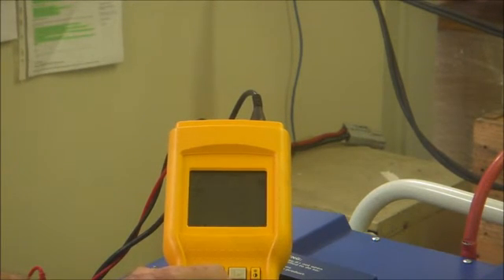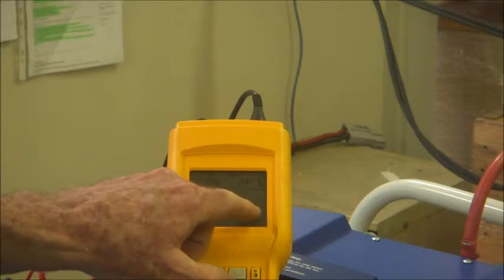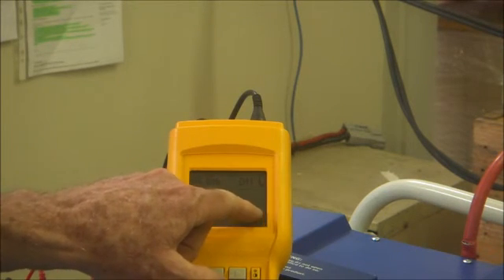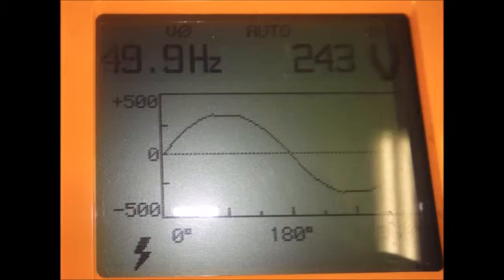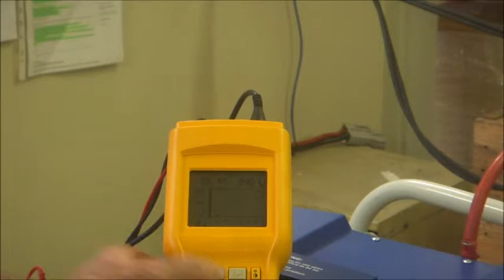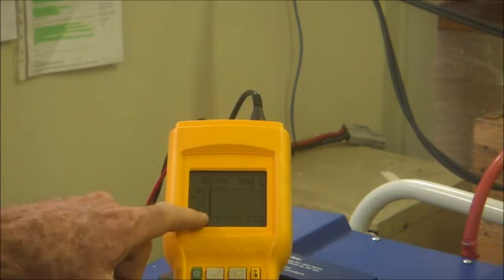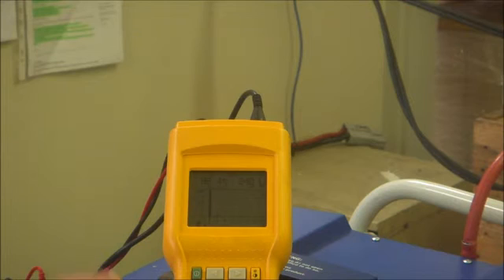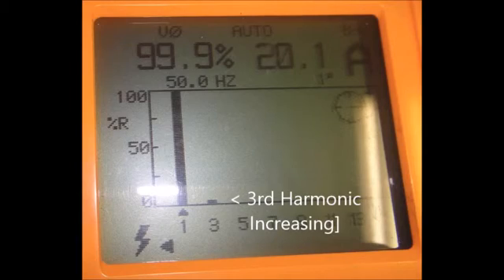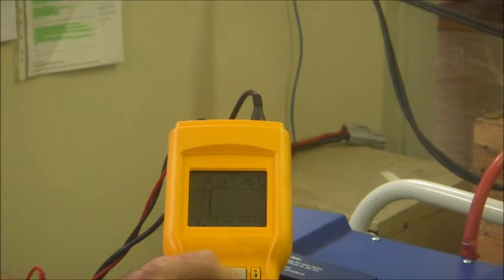You can start to see, let's have a look at the voltage. You can start to see a little bit of flattening at 10% on the waveform here, which is indicating the harmonic effect. And now you can start to see the third harmonic coming in. So you've got the fundamental here, and you've got the third harmonic there. The second harmonic is minuscule. The third harmonic is 10.6%, and the other harmonics are not there.